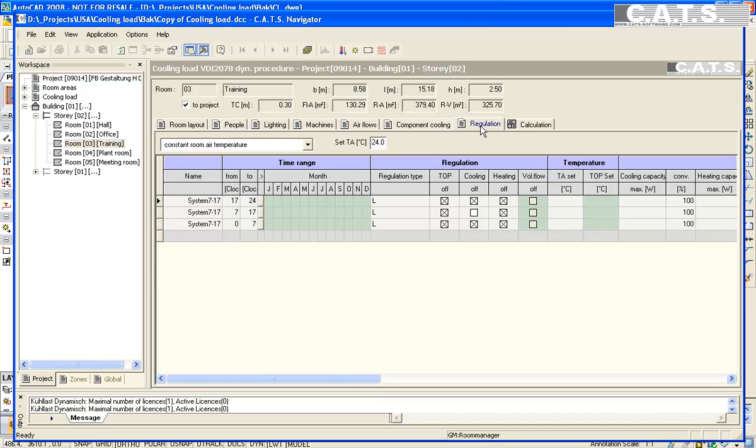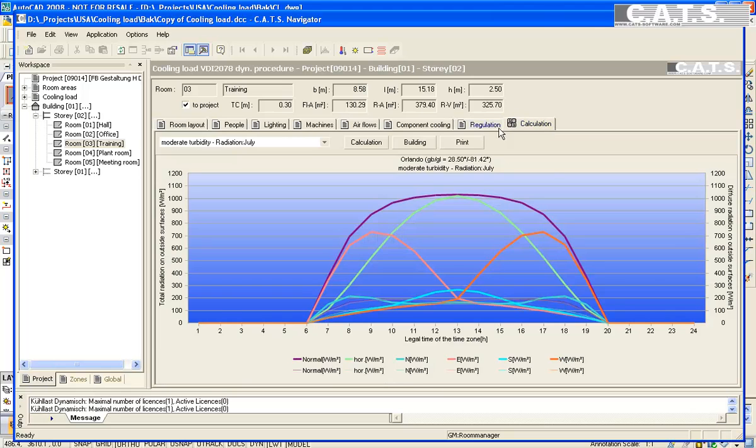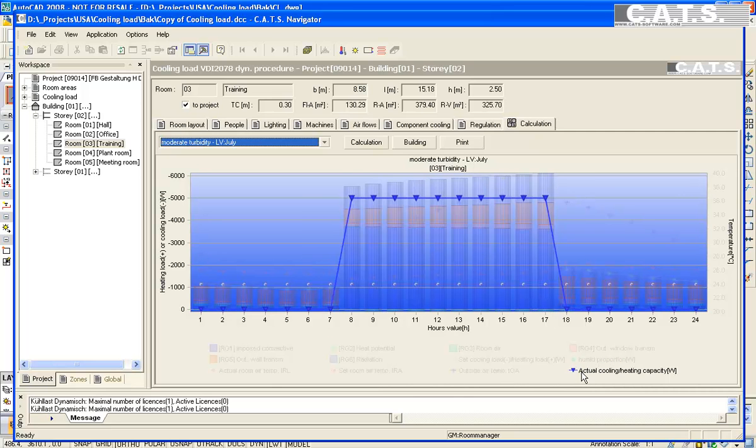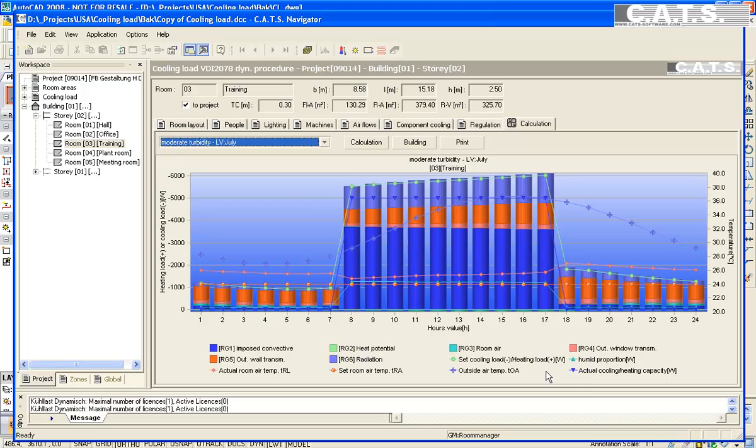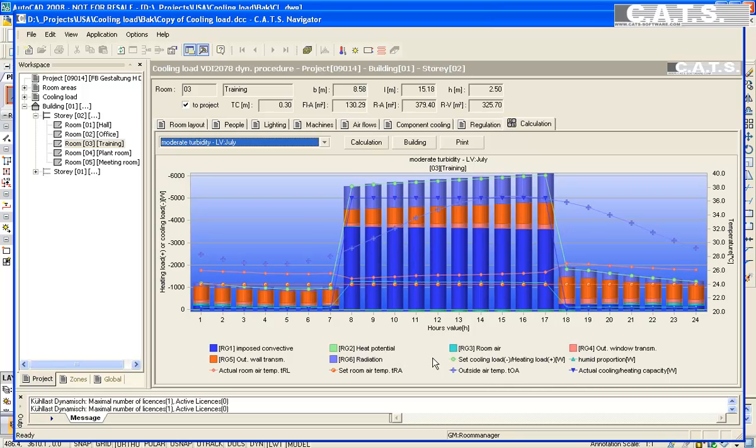We are now going to limit the cooling capacity to 5000 watts. We enter 5000 in the capacity column and recalculate. We first see the curve at 5000 watts capacity. The cooling load, however, is up to 6000 watts.